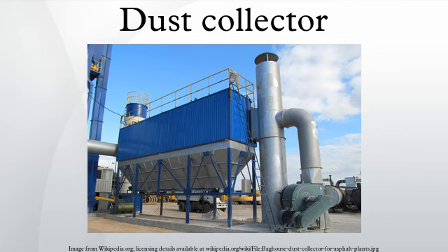Types of dust collectors. Five main types of industrial dust collectors are: inertial separators, fabric filters, wet scrubbers, electrostatic precipitators, and unit collectors. Inertial separators. Inertial separators separate dust from gas streams using a combination of forces, such as centrifugal, gravitational, and inertial. These forces move the dust to an area where the forces exerted by the gas stream are minimal. The separated dust is moved by gravity into a hopper, where it is temporarily stored.